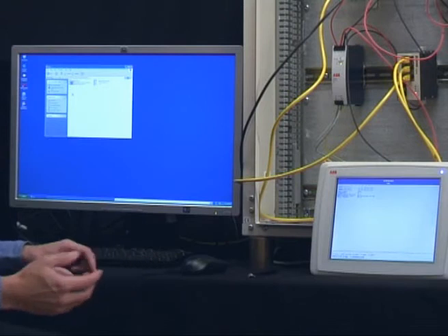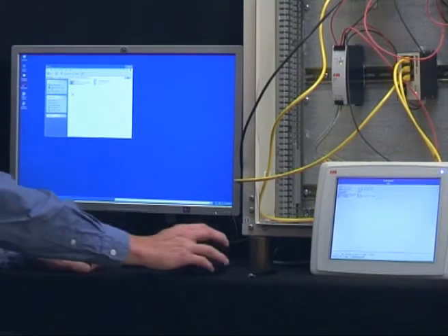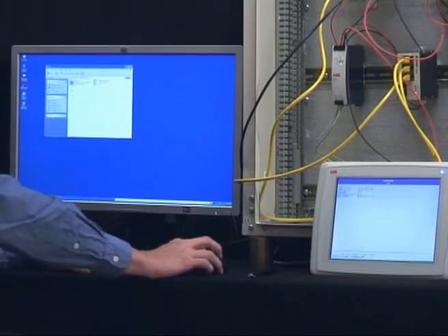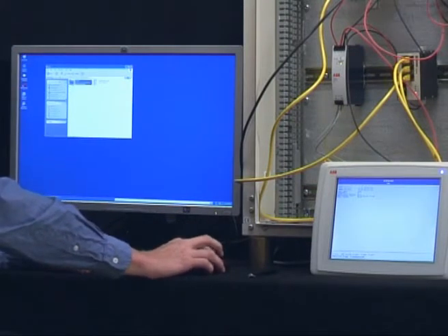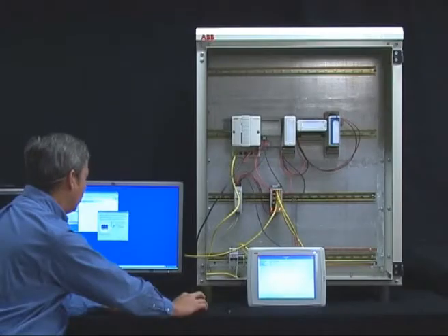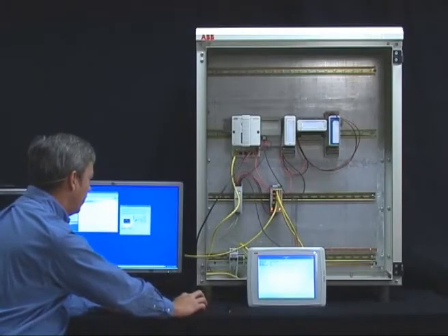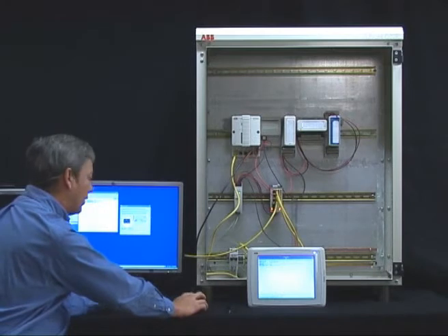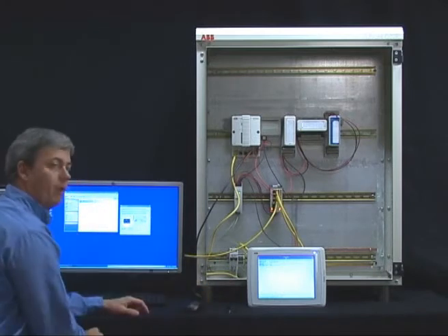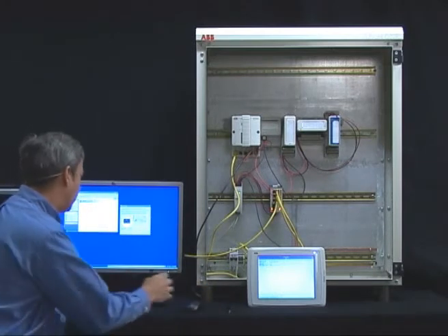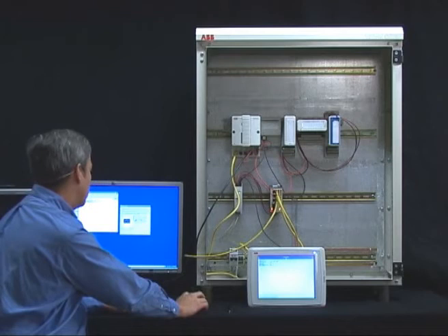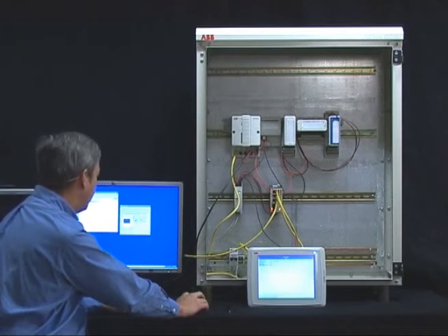You can see that there is an IML folder. You double click on the IML folder and you get into the image loader. Here you can see that the first step we have already taken care of: putting the DIP switch in the right position and restarting the panel.